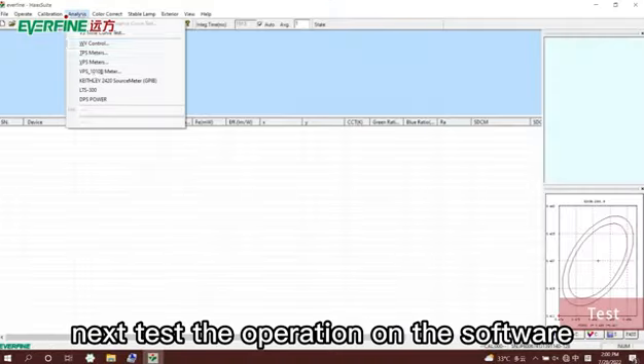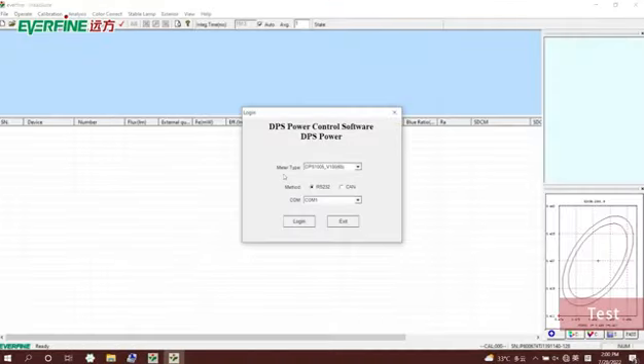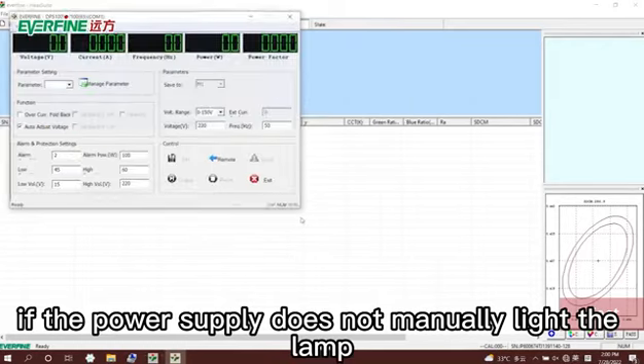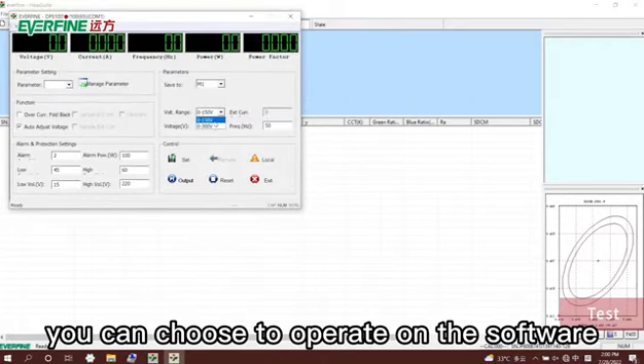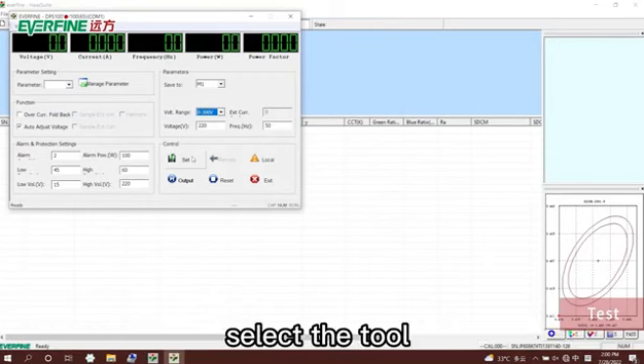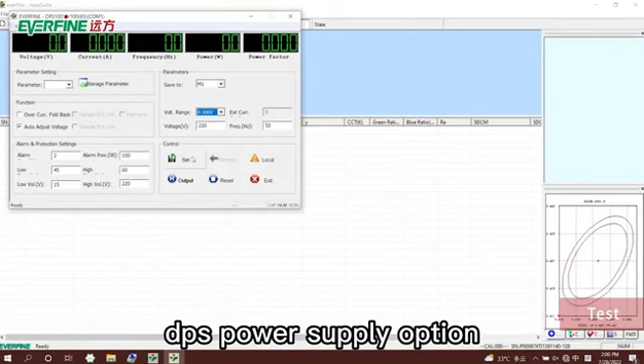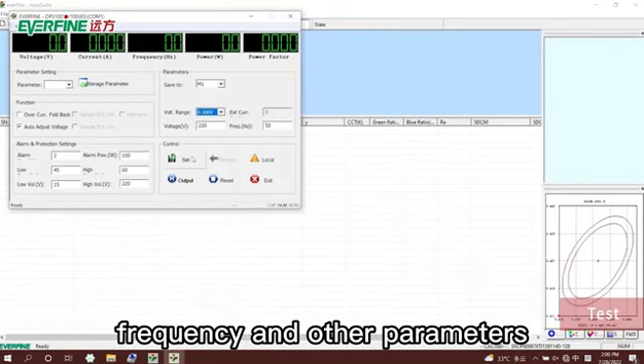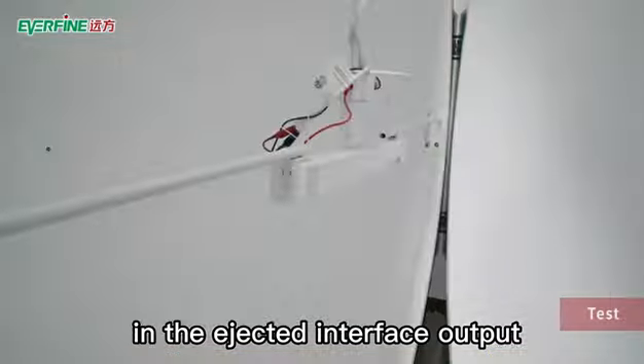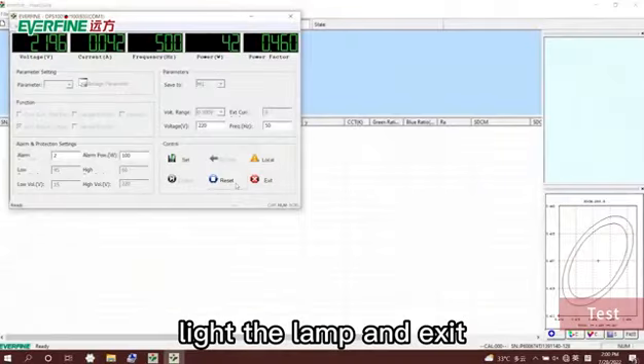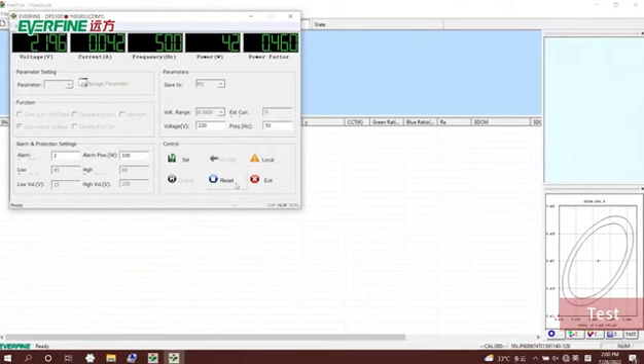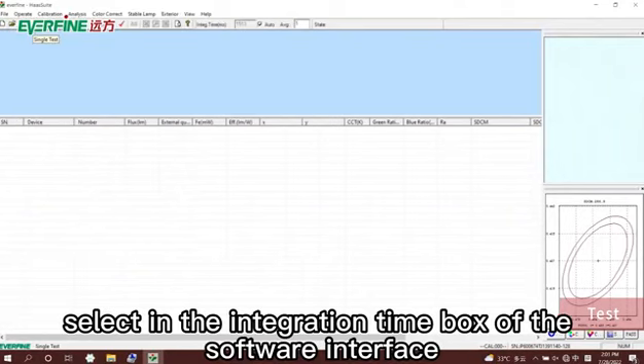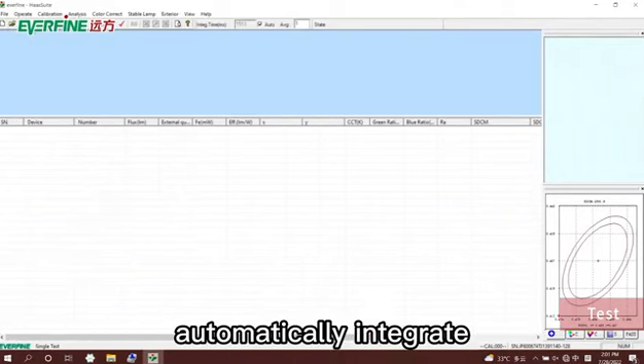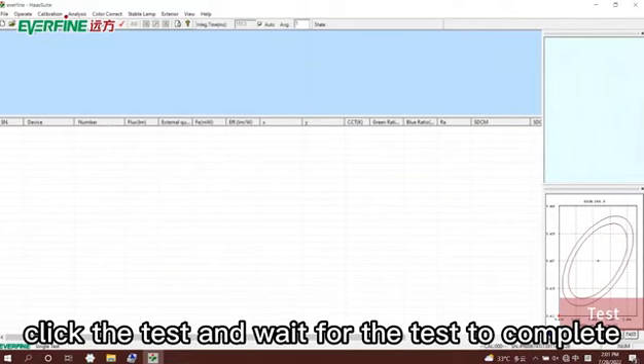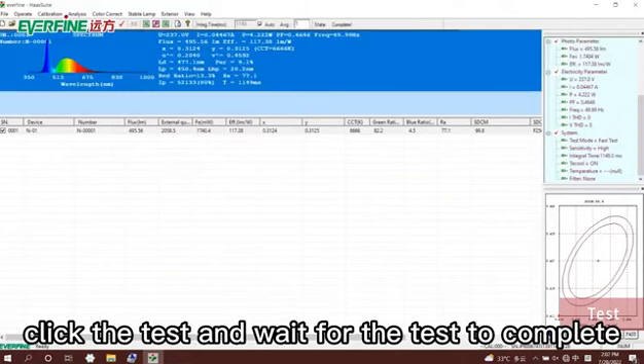Next, test the operation on the software. If the power supply does not light the lamp manually, you can choose to operate on the software. Select the Tool, DPS Power Supply option, and set the voltage, frequency and other parameters in the pop-up interface. Output, light the lamp and exit. Select automatic integration in the integration time box of the software interface, click test, and wait for the test to complete.